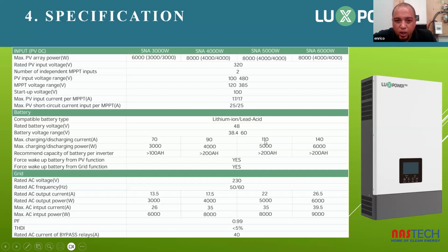So when you do your power formula, when setting your inverter for battery charging and discharging, you don't want to lose the lifespan of the battery very fast, and you also don't want to burn out any components inside the inverter. So the power formula is power equals voltage times amps.